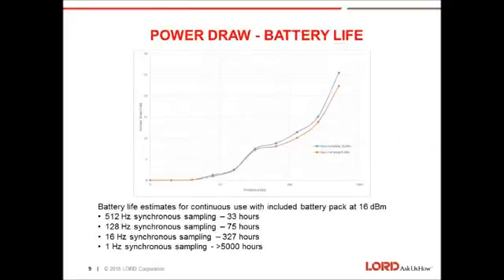This next chart is for the power draw and battery life. So you can see the two lines. The first is sync sampling at 16 dBm, and the second is sync sampling at 0 dBm, so our high power setting, our low power setting. You can see it's a pretty small difference between the two, and then below 16 Hertz there's really no difference between them. But using the 16 dBm and the included battery pack, we're looking at conservative life estimates of 33 hours for 512 Hz synchronous sampling, 75 hours for 128 Hz synchronous sampling, 327 hours for 16 Hz synchronous sampling, and well in excess of 5,000 hours for 1 Hz.